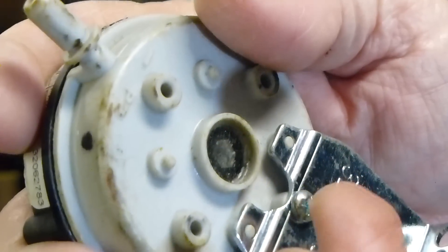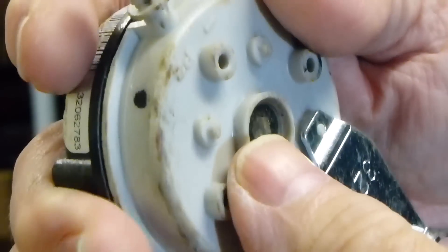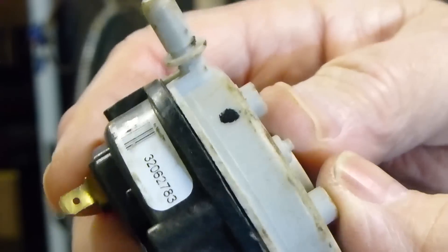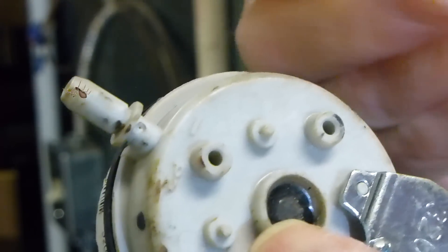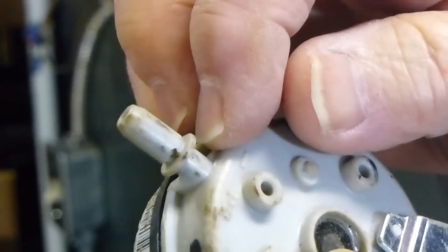Now, like I said before, you could recalibrate this switch if it was out of calibration, but that could really void your warranty because you're messing with something that is preset. I wouldn't recommend doing that—that would be a bad idea. Plus, you never know what's going on on the inside of this particular switch. I mean, it could be way out of calibration because of moisture, debris—like I said—holes in the diaphragm, or the bleed port being partially plugged or plugged. And that could cause everything to go out of calibration.